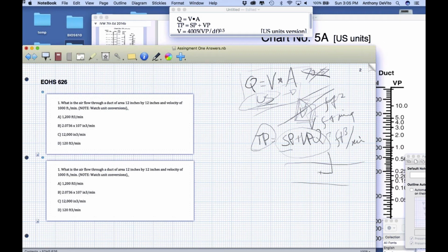If you imagine a device sitting in this ductwork with an opening here, measuring this pressure, that pressure obviously has a velocity pressure component. But since the static pressure acts in all directions, including the direction that the velocity pressure is going, it's really measuring the total pressure. If we want to measure the static pressure, we would need something open to the side of the ductwork, so it's not being influenced by the movement of the air. That would be our static pressure.